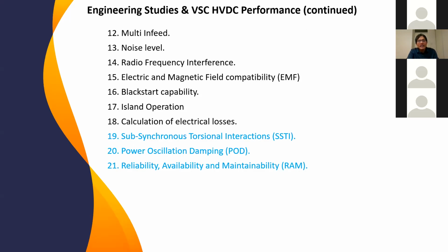Radio frequency interference to evaluate high frequency interference generated by the converter station. EMF to prove the electric and magnetic fields at the converter station do not induce current, leading to overheating in other important equipment. Black start capability to prove the VSC converter station is capable of supplying power to an area where the power grid is not available.